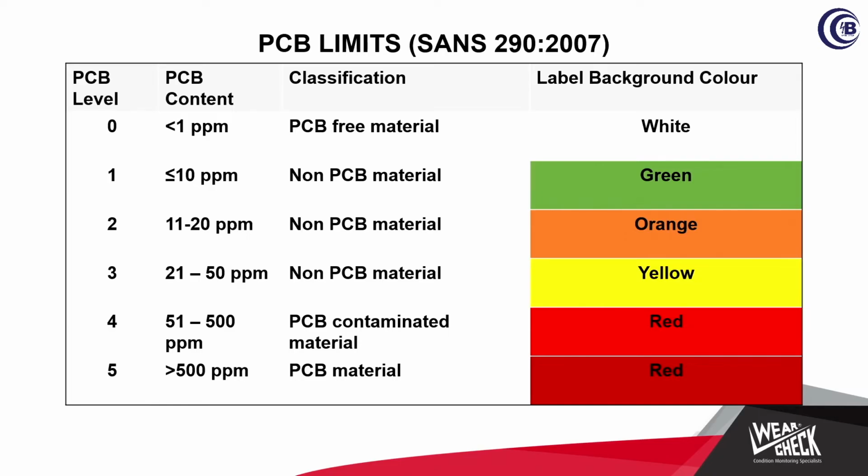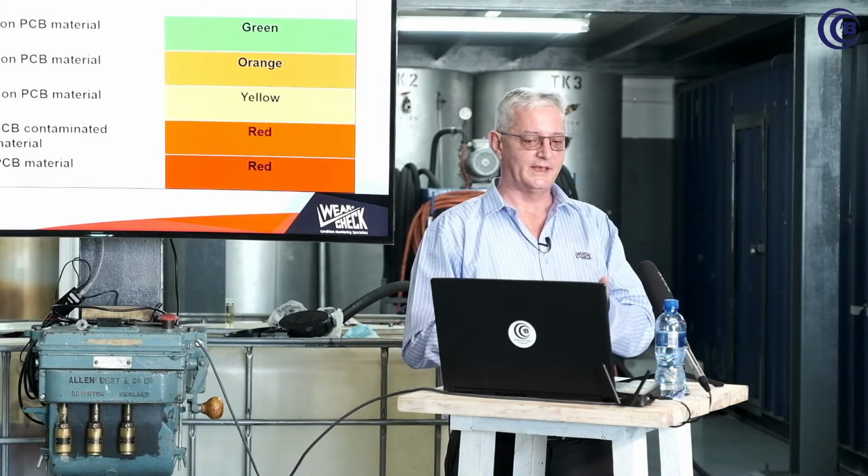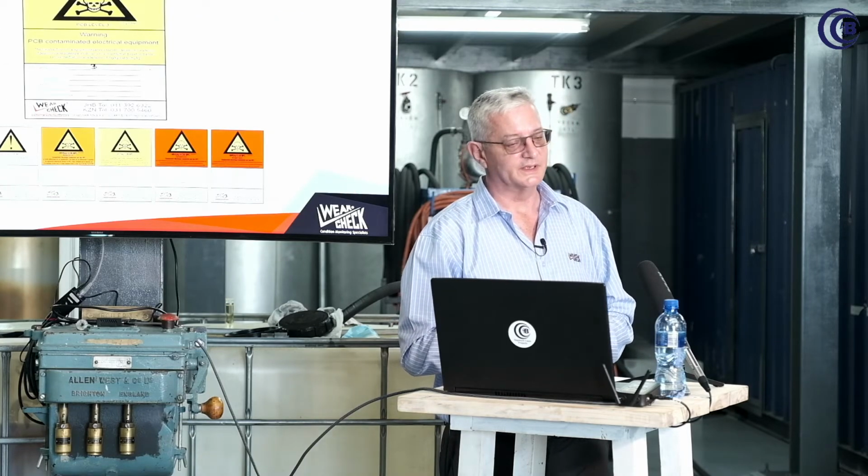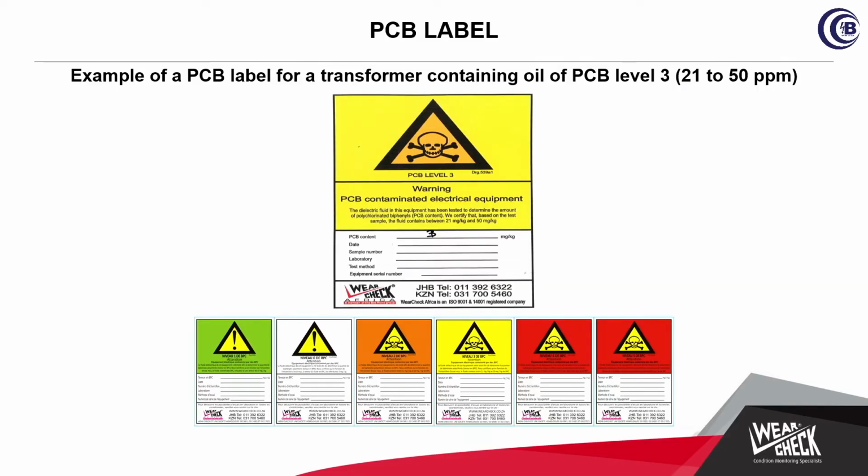Now, years ago, there were only basically categories of less than 50, above 50 and above 500. SANS 290 SABS has decided no, that doesn't work. We need to put it in different categories. So you've got now 5 categories for your PCB oil. The changing of the oil is still, if the oil is above 50 ppm, then you need to do something about it. If it's below 50, it's still okay. So now we just have different stickers and someone making money out of the printing of the stickers. That's just an example of the different colors of the stickers that need to be on your transformer.